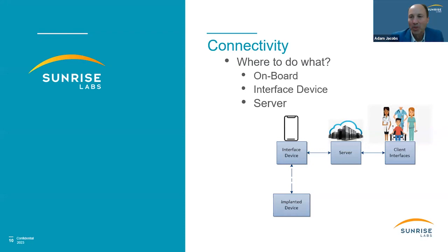The question that always comes up is where to do what. So one option is to take all this data and send it up to a server and use the giant power of a server farm to do everything you want. But the point is that in implantable devices, you're very power limited. And since communication is the limitation, very often the things that you want to do on the actual device are signal processing beforehand. And of course, you would always do safety operations on the implanted device. You never want to go out to an external device for something that's safety related.